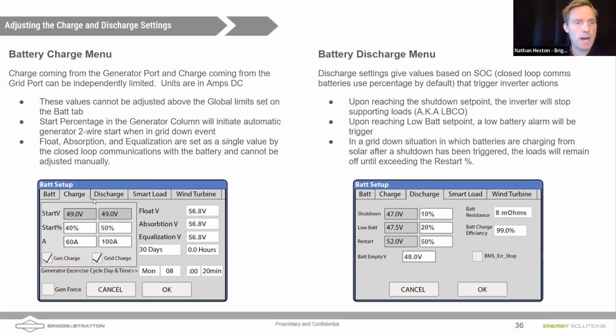On the charge tab inside of a Sol-Ark, you will have the option to enable generator charging with this checkbox here, and then this column. This column is related to the maximum DC charging rate. So I do want to point that out. When we have 60 amps DC in that column, it's referring to the charging rate of the batteries. The batteries are at a nominal 48 volts DC, so that's 60 amps of DC charging.